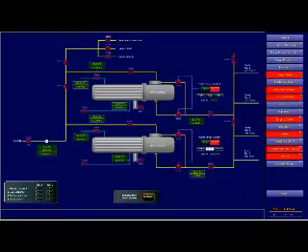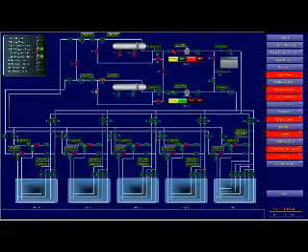Heaters we are also not using, they are also secured. But we have got the glycol alarm, very simply. At the moment our glycol system is running, but delivery pump number 2 has got some pressure problems. So we have got this alarm, and of course we have acknowledged the alarm. Can you see the heater?